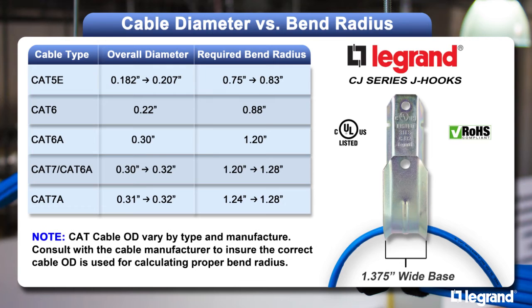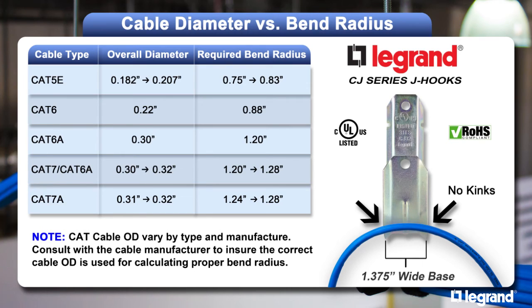For instance, the minimum bend radius of a CAT-6A cable with an outer diameter of 0.3 inches should have a minimum bend radius of 1.2 inches. Use a cable support that has a base wide enough to inherently maintain the minimum bend radius of your cable. Cablofil's CJ Series J-hooks have a wide base support and beveled edges that maintain a minimum bend radius of 1.375 inches.